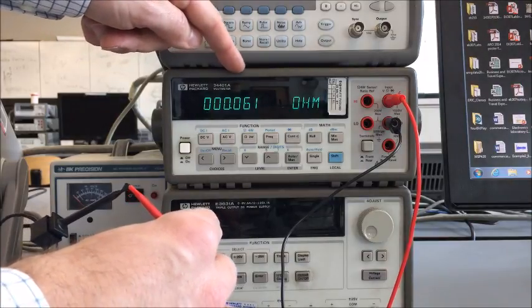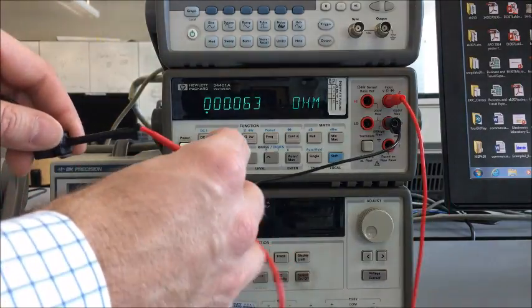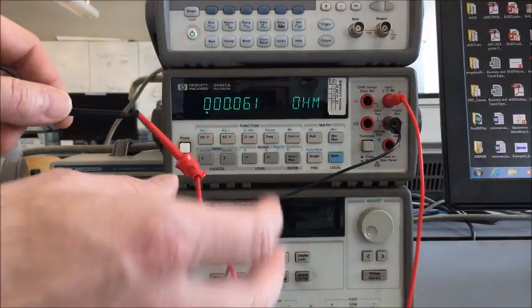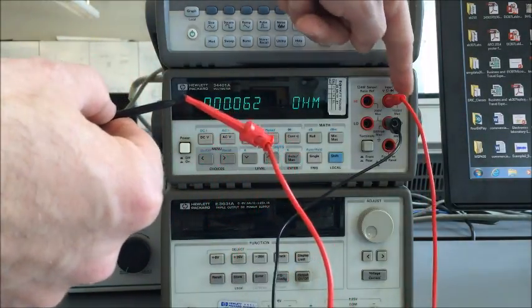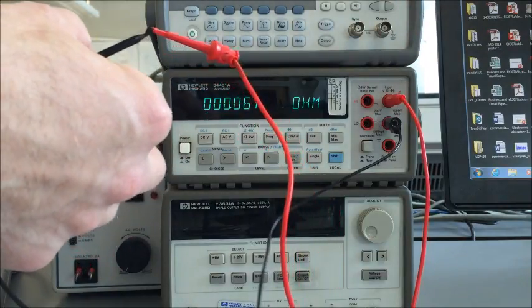We have 60 milliohms, which is what we're measuring in the instrument. That 60 milliohms could just be the contact resistance of the wires and the connectors in the instrument. Things are looking good.